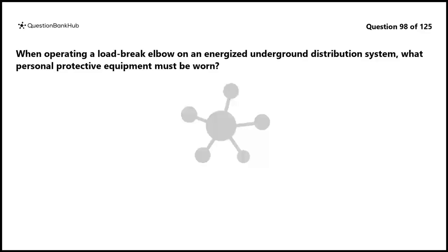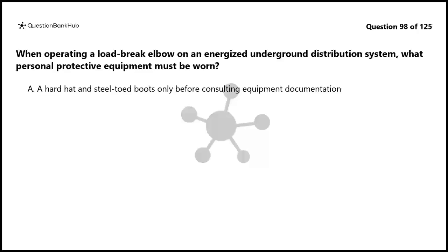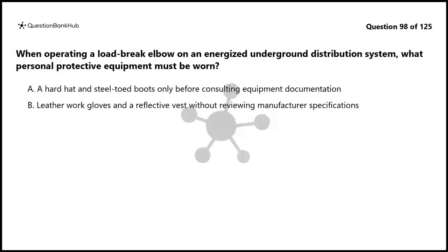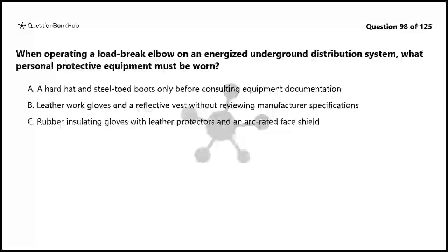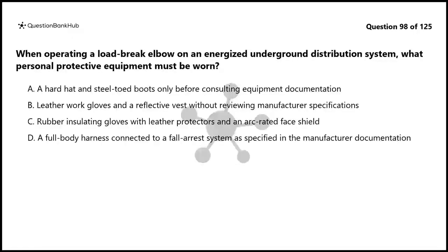Question 98. When operating a load-break elbow on an energized underground distribution system, what personal protective equipment must be worn? A. A hard hat and steel-toed boots only before consulting equipment documentation. B. Leather work gloves and a reflective vest without reviewing manufacturer specifications. C. Rubber insulating gloves with leather protectors and an arc-rated face shield. D. A full body harness connected to a fall arrest system as specified in the manufacturer documentation.